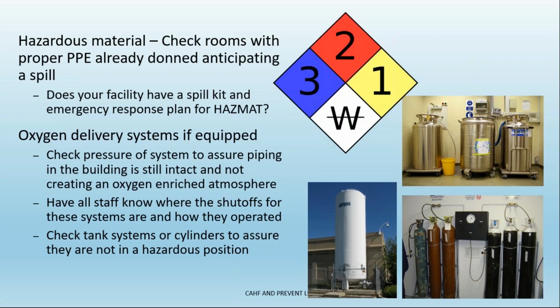Check your oxygen delivery systems if you have them. Make sure that the pressure in the building is not dropping. It's still intact. You can check all the gauges. That's going to indicate if you have any leakage inside the walls that are not visible. Make sure your staff know how to turn off the shutoffs and all these systems and how they are operated. Make sure your evening and night shift staff know how to work on these types of systems as well. Check the tank systems or cylinders to assure that they are not in a hazardous position or have any kind of leakage at all.